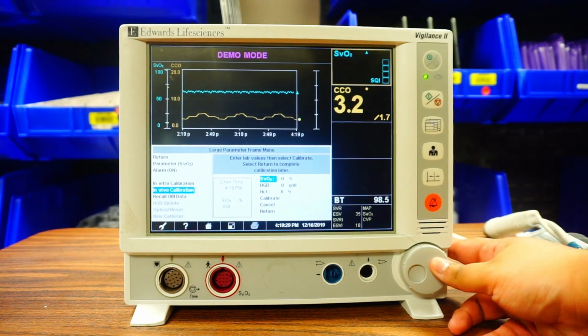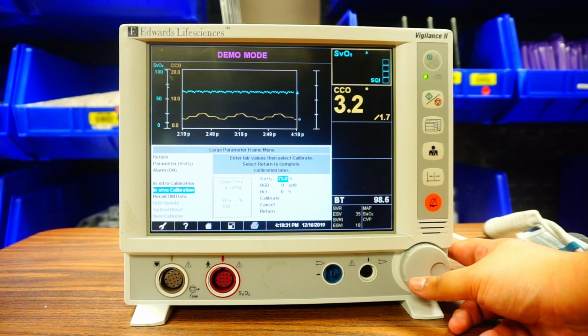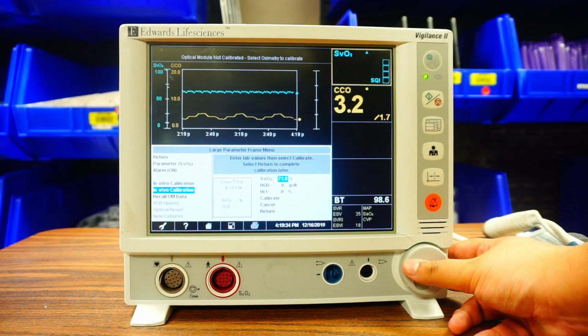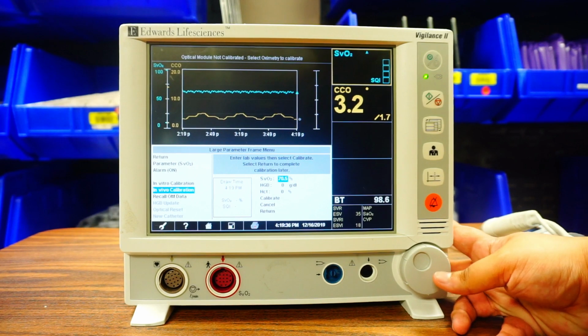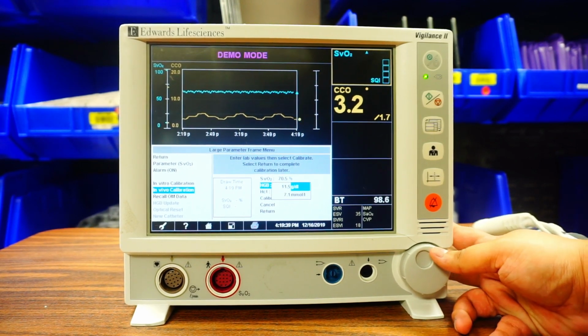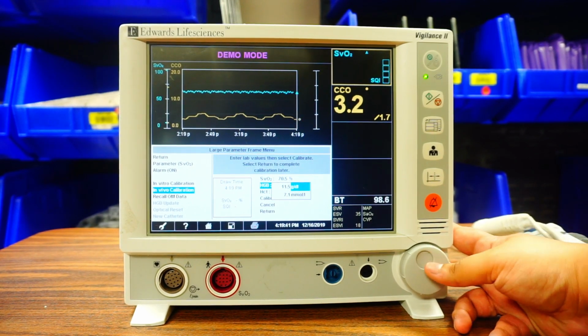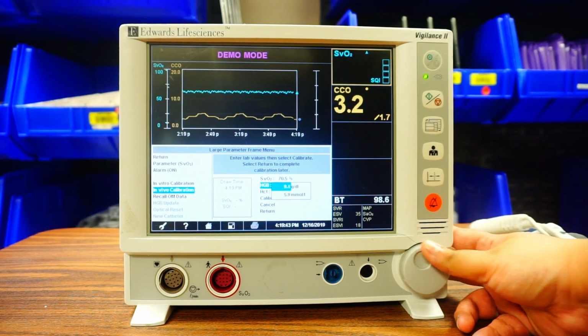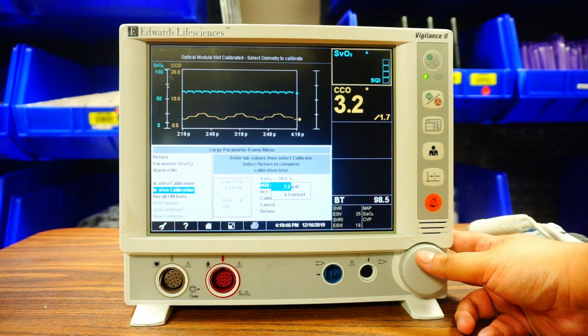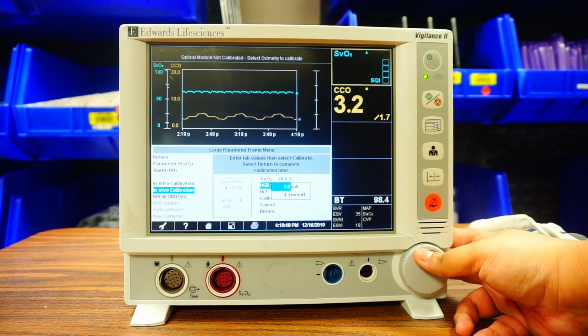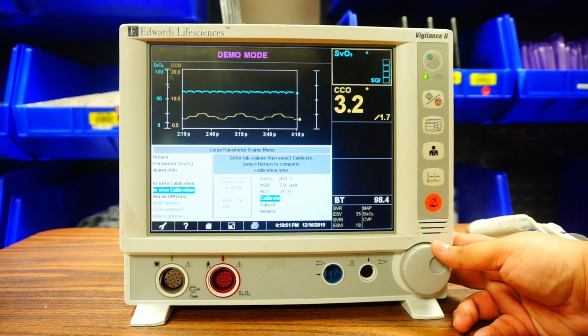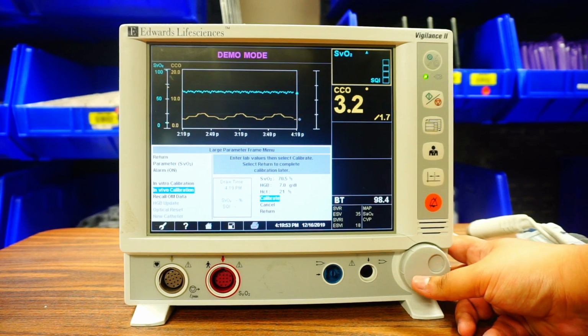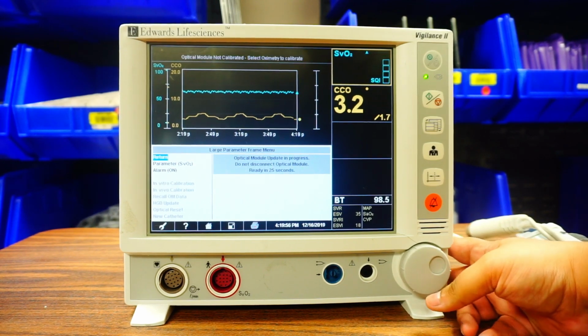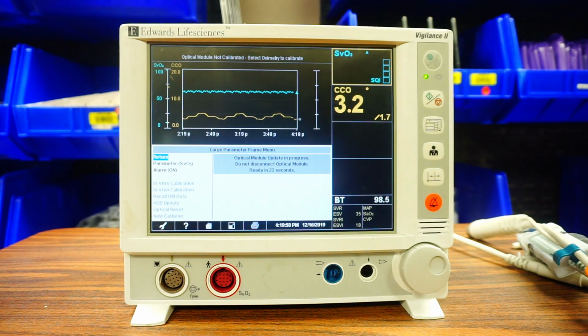So we'll say my SVO2 was just say 70.5, and then I'm going to put my hemoglobin in, and we'll just say it was 7. Clicking that. Hematocrit's automatically going to pop up. Once those 3 values are put in, I'm going to go ahead and press calibrate. It's going to take 25 seconds for it to get that value, and then I'm going to be continuously seeing what my SVO2 is up here.